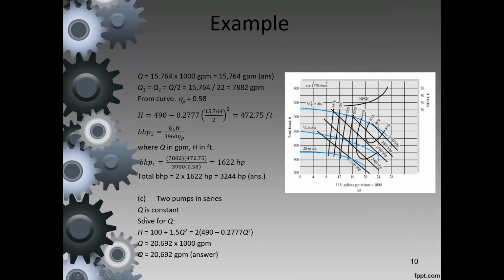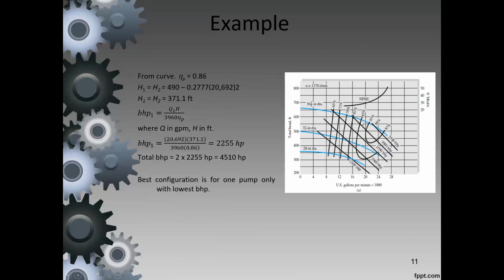Q is constant. Solve for Q. H is equal to 100 plus 1.5 Q squared. Ano yung Q doon is equal to 2 times 490 minus 0.277 Q squared. That total yung head mo, di ba? Ang Q mo ito. So Q is equal to 20.692 times 1,000. So Q is 20,690 GPM. Then from the pump curve, this is 0.86.